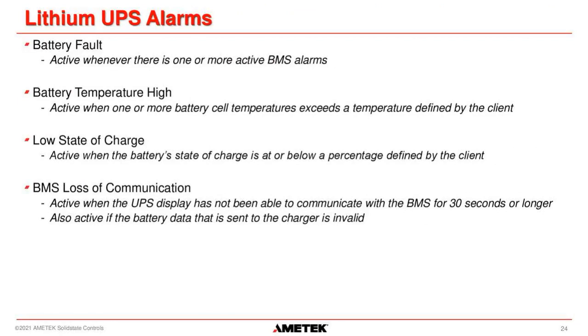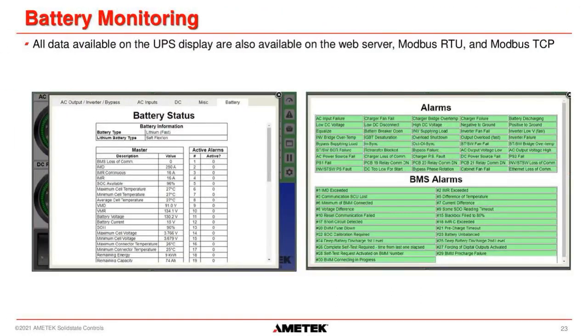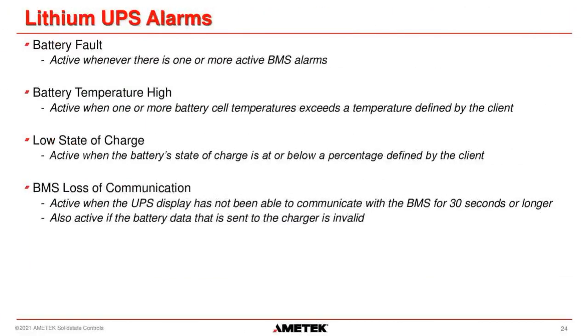We've added 4 new alarms that are standard for lithium-ion batteries. We have a battery fault alarm. This alarm is a UPS alarm that can be mapped to a Form C contact or an LED on the front of this UPS, and it will activate anytime one of the alarms in the BMS alarms activates. So it acts as a common alarm. If the battery fault alarm activates, it'll also activate the common alarm on the UPS.